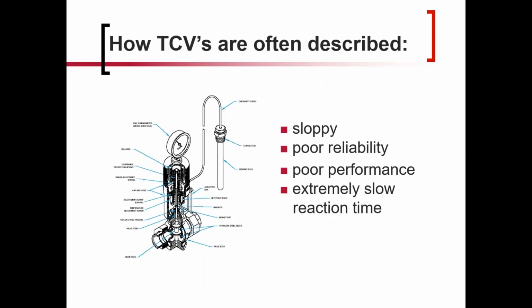So one of the realities of temperature control valves is they often won't have a great reputation. People will say, oh, they're sloppy, or they have poor reliability or poor performance or extremely slow reaction time. And depending on expectations, to be honest with everyone that's on here, those can be true. So for example, if you expect a mechanical valve to control within 1 degree plus or minus, you probably will find it to be sloppy, because it's very rare that they will control to that much accuracy. Extremely slow reaction time, again, that is a perception thing and can be accurate depending on expectations.